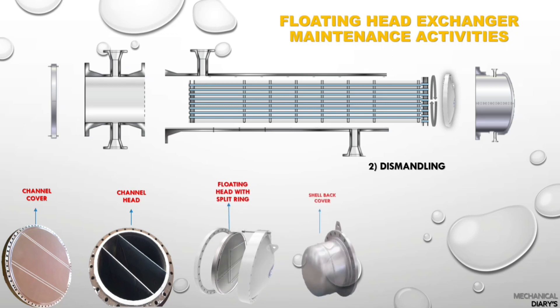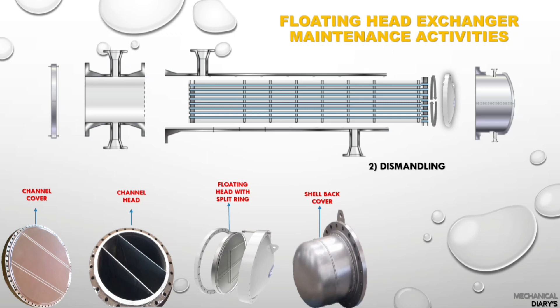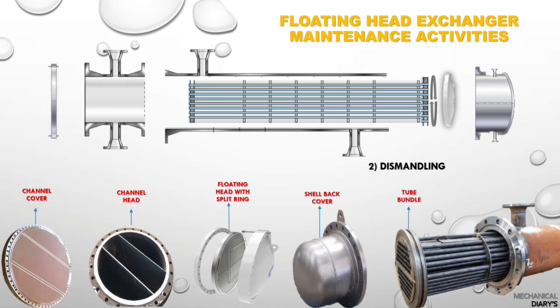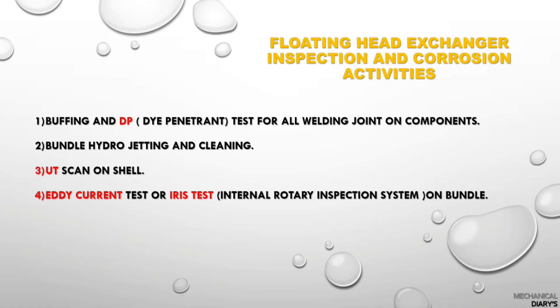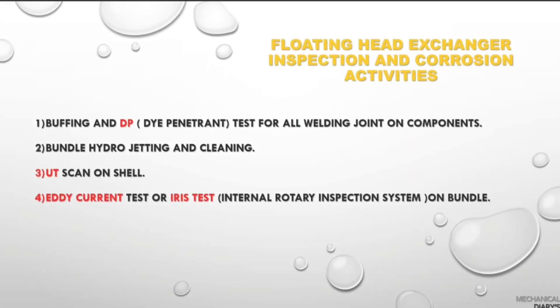Dismantling has a specific procedure. First, remove the channel head cover, then the shell back cover, then the floating head, then the channel head. Last, pull out the tube bundle. Once you pull out the bundle you can start the inspection and corrosion activities.